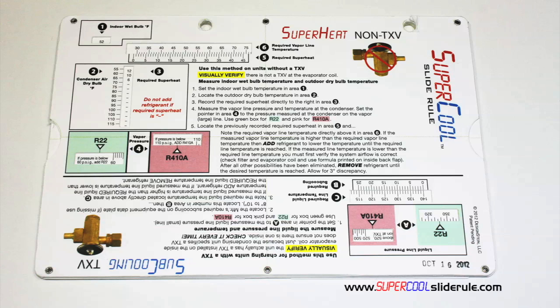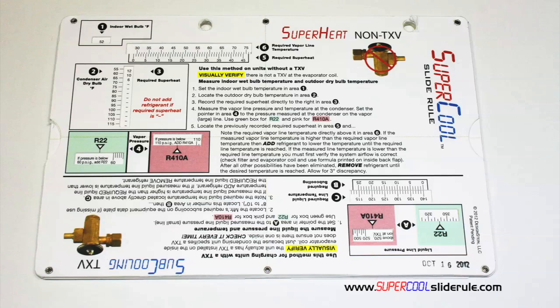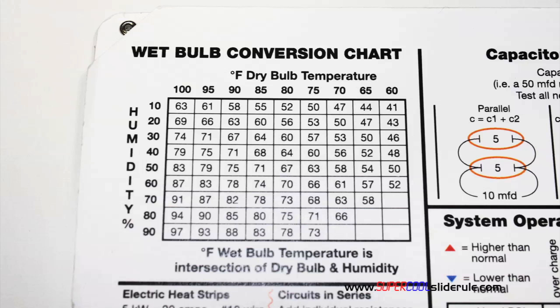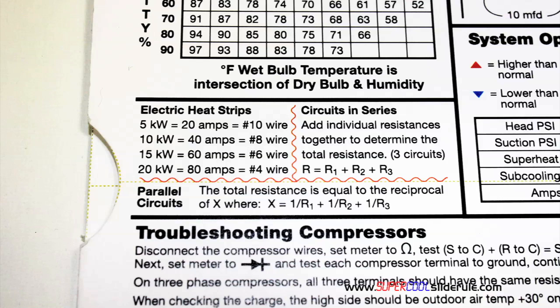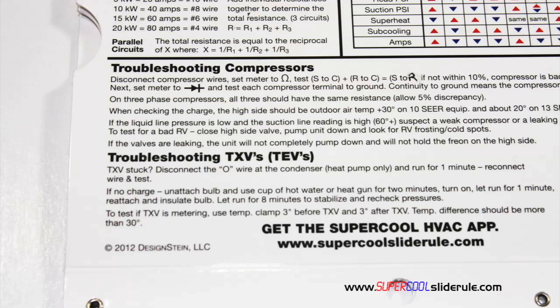This one tool will allow you to charge a system with R-22 or R-410A in either the superheat or subcooling method. The back cover contains required formulas, capacitor rules and practices, a wet bulb conversion chart, how to perform computations on series or parallel circuits, an electric heat strip guide, and a complete system troubleshooting diagnostic chart.